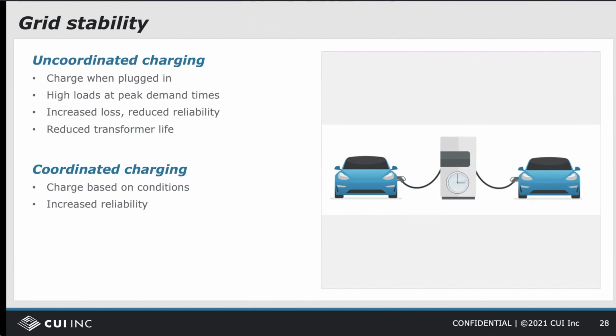Uncoordinated charging is when the charger starts charging immediately when plugged in, or potentially after a defined delay, and doesn't consider what else is connected to the grid or any other conditions. This can cause problems if everybody decides to charge their car when they get home from work. It can lead to voltage surges and sags, increased power losses, and reduced reliability of an already aging grid. And studies have shown that as EV adoption increases, uncoordinated charging will cause a significant increase in peak load demand.